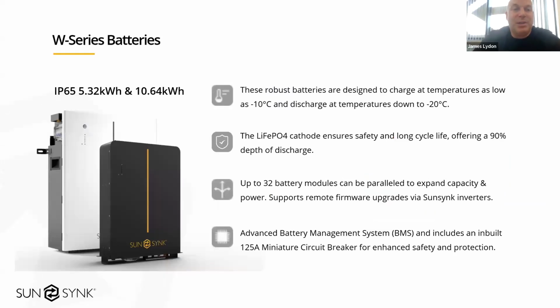Okay, our low voltage batteries. So the W series batteries. These are available in two sizes: a 5.32 kilowatt hour and a 10.64. The cells within the W series batteries will charge down to -10 and discharge down to -20. So there is still a level of derating the colder it gets, but they will still charge and discharge. LiFePO4 is standard, so lithium iron phosphate is really safe, and they all have a 90% depth of discharge.